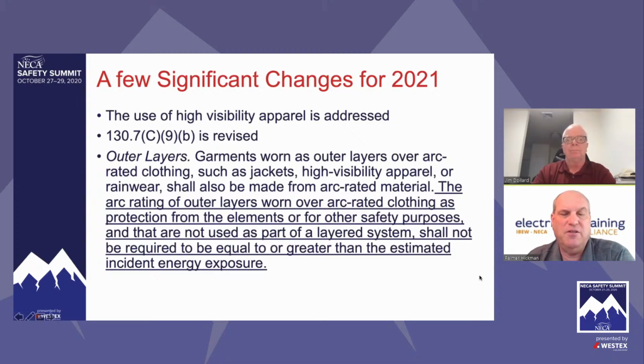The other thing you see is underlined text added for clarification. So if my hazard assessment shows I have to wear 12 calories, does my high vis vest have to be 12 calories? Good luck finding a 12 cal high vis vest. Or what about my rainwear, does it have to be 12 calories? This extra language clarifies that: the arc rating of outer layers worn over arc rated clothing as protection from the elements or for other safety purposes, and that are not used as part of a layered system, shall not be required to be equal to or greater than the estimated incident energy exposure.